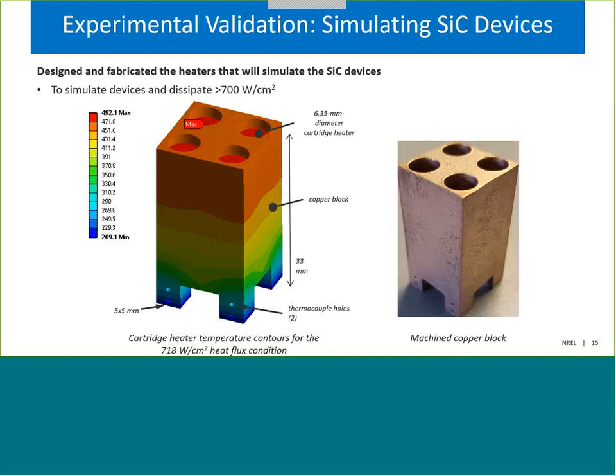On the left, you see the temperature contours from the FEA. This is for the 718 watt per centimeter squared heat flux condition. We are predicting very high temperatures on the cartridge heaters, but they are within the vendor stated limits. The temperature at the base of the copper block, which is the part that simulates the silicon carbide devices, is about 210 degrees, which is consistent with all of our other modeling work.